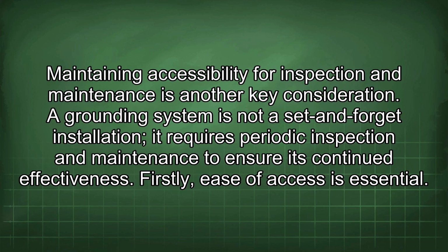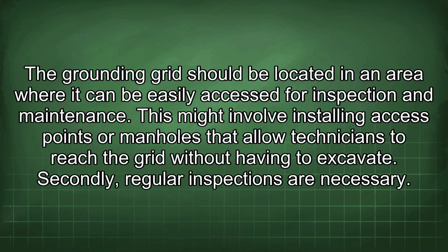Maintaining accessibility for inspection and maintenance is another key consideration. A grounding system is not a set-and-forget installation. It requires periodic inspection and maintenance to ensure its continued effectiveness. Firstly, ease of access is essential. The grounding grid should be located in an area where it can be easily accessed for inspection and maintenance. This might involve installing access points or manholes that allow technicians to reach the grid without having to excavate. Secondly, regular inspections are necessary.